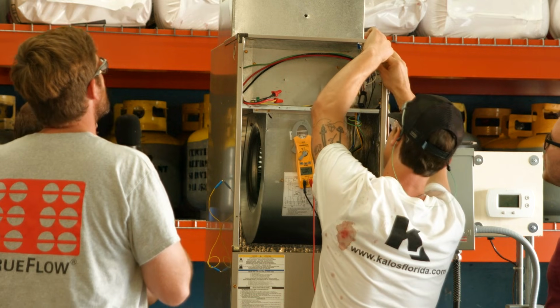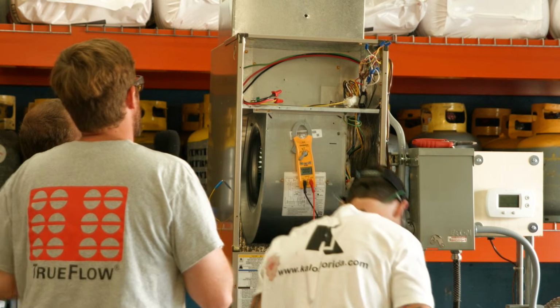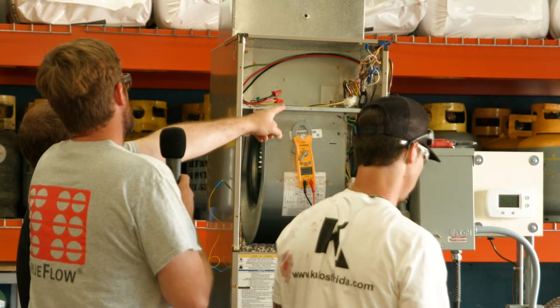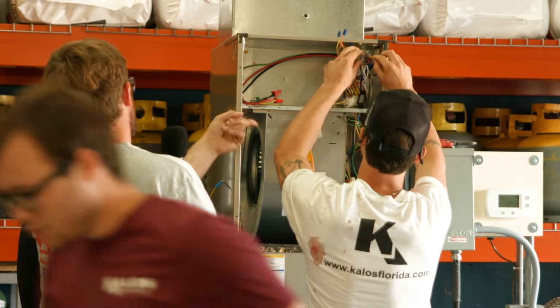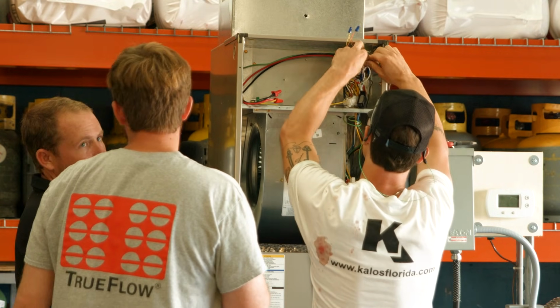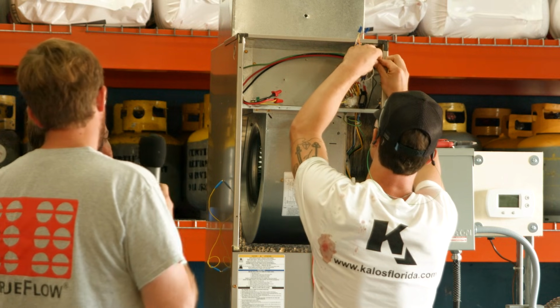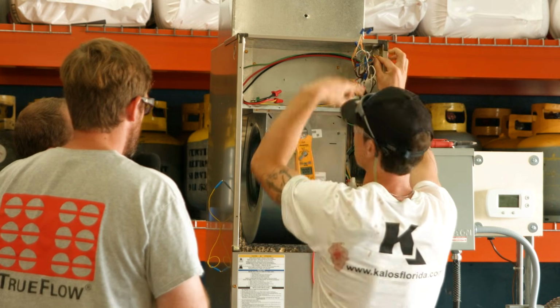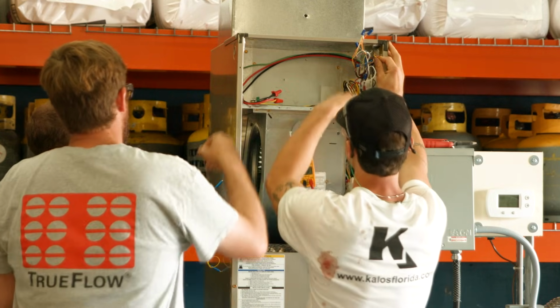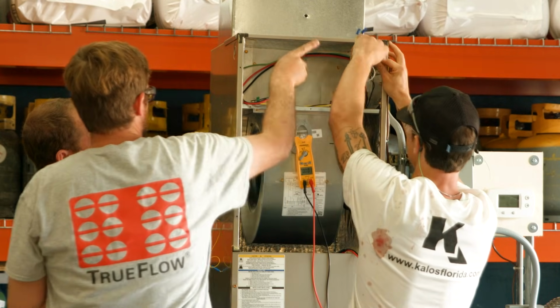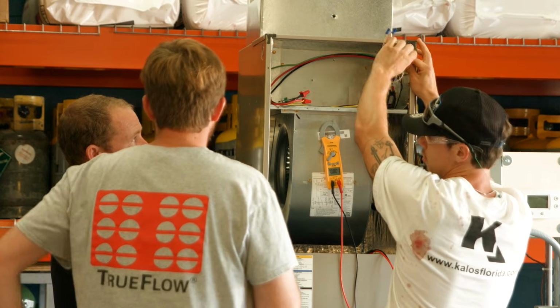Now on this one, the way that plug is, once you unplug it off of there, you would still be bonded to ground on your common. So I would just pull those two off and start there. I would pull these two wires off and just start sticking leads in wire nuts, just ohming directly.